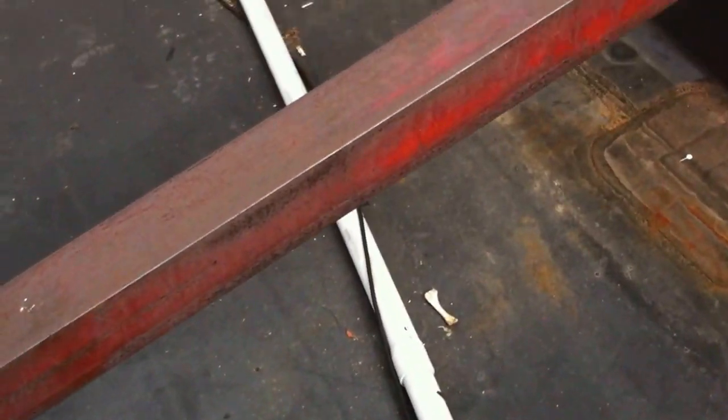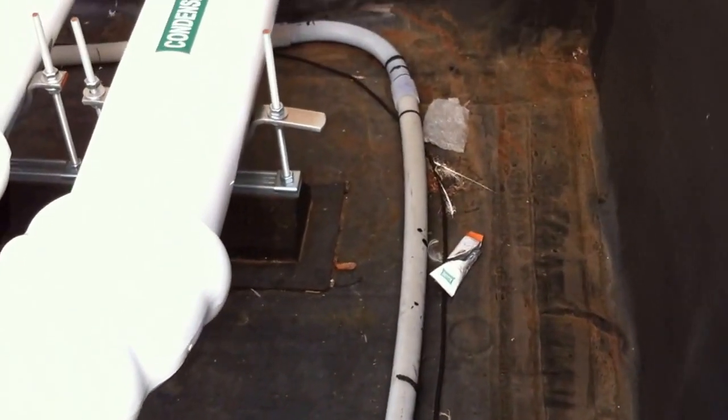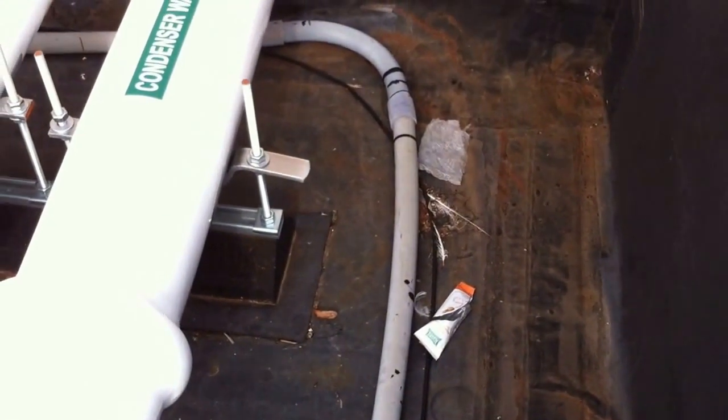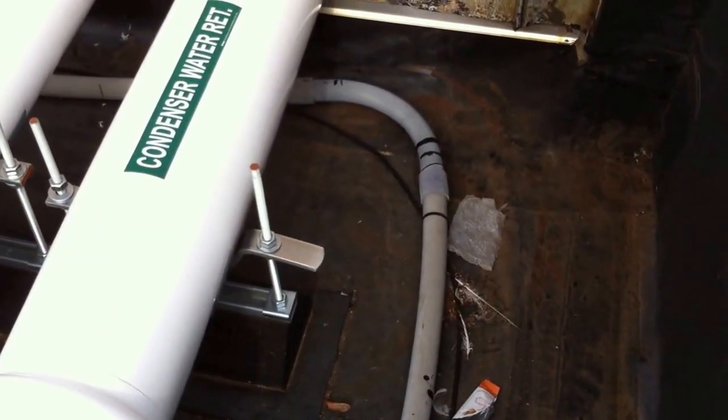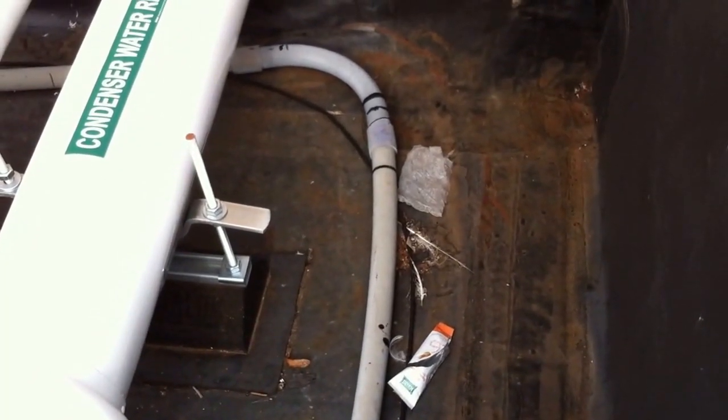Also, NEC 352.30 contains requirements for supporting and securing PVC, and this PVC has zero securing — none. It's just flopping around up here on the roof, and this is why the pipe is broken. This is Russell Blank, NEC consultant for EC&M magazine.